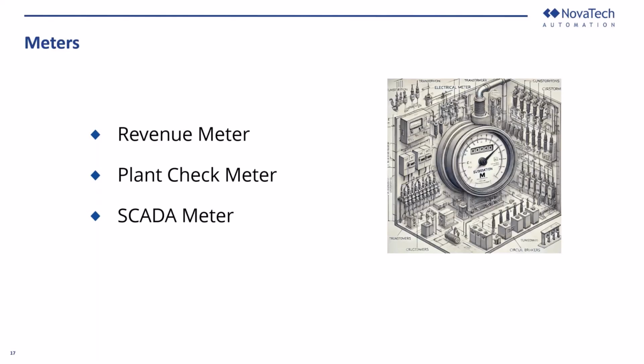The third one, the most common, is the SCADA meter. It's used for real-time monitoring and control, and it gets parameters like voltage, current, power, and frequency, and is used in conjunction with SCADA. So all these points are fed to the SCADA. For logging purposes, it continuously logs the energy consumption data for analysis and reporting. It's typically used in substations, grid control centers, and distributed power systems. That's the very common SCADA meter we have.